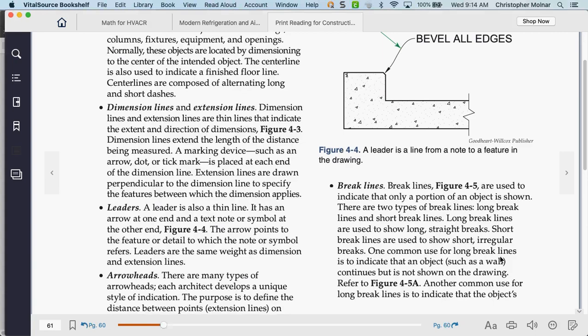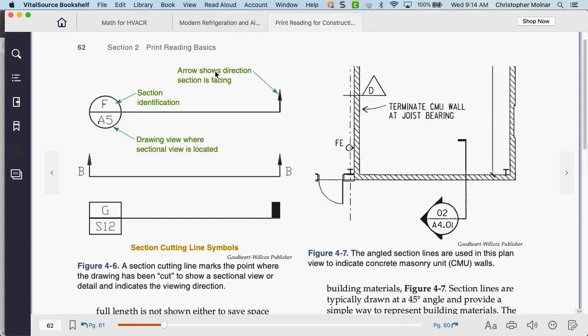Section cutting — the arrow shows the direction the section is facing. So if you see this on a print pointing to something like a mechanical component, you need to find where this A5 is because there's a more broken-down version of that. For example, if you're installing a boiler, they might have a breakdown of exactly how the piping has to be laid out at section A5. Any time you have a print and another section number, you have to look for that additional section to see if there's a blown-up view.